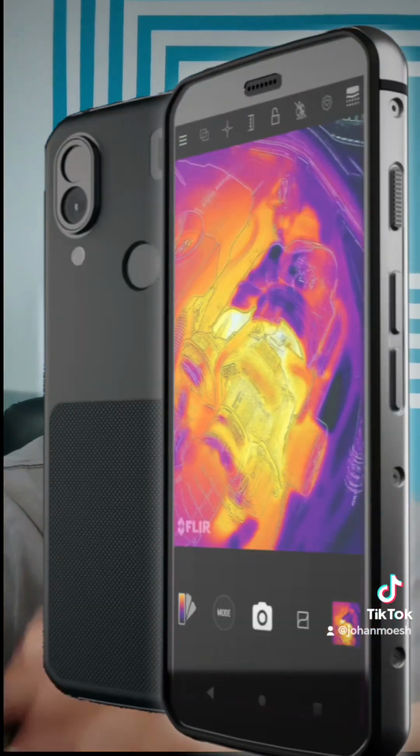You get Cat phones that have got the thermal in, FLIR, not too bad. Also, Blackview also has. We will look at certain entry level ones, so that you can just make sure, especially on the panels and your MC4 connections, and also in your combiner boxes. Like I say, the thermistor, very important, into your combiner box. Any loose connection, it will arc, it will start to get hot. You will get a notification. Prevention is always better. And then also, like I say, into your inverter, if you can take it out, but you cannot always, because again, the warranty.